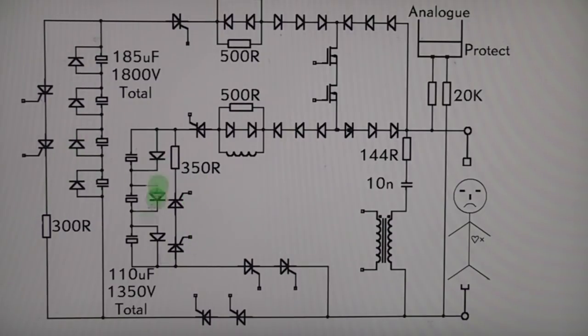This is this big blue resistor, there's a couple of series thyristors to discharge this capacitor and again this smaller bank's got its own discharge resistor and its set of thyristors. Each bank goes through this little network, we've got an inductor here, this is going to be to control the rise time of the pulse waveform. I think these diodes are going to be to avoid any reverse kickback through that inductor when the current's turned off and I'm guessing this resistor is probably also to damp down and control the waveform.